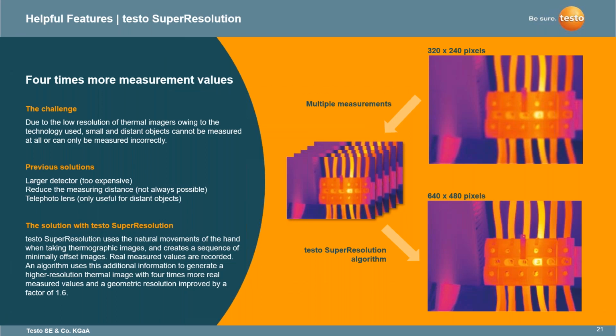Going into the features now, one of the helpful ones is Testo Super Resolution, which every imager from Testo has the ability to use. Due to the low resolution of thermal imagers and the technology used, small and distant objects cannot be measured at all, or can only be measured incorrectly. Previous solutions have had larger detectors, which raise the prices of imagers, and obviously cost is a big aspect when bringing in a thermal imager because it is a big investment.